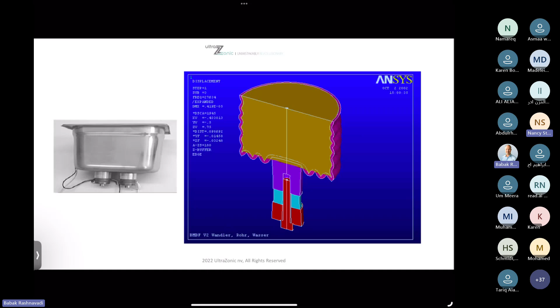So that's why your stainless steel may not be the 304 or whatever. It's actually a duplex stainless steel that you have to use, because the duplex stainless steel is tougher, and it's also very reliable when it's glued with the transducer, so you will not break down the stainless steel. Okay, next slide, please.